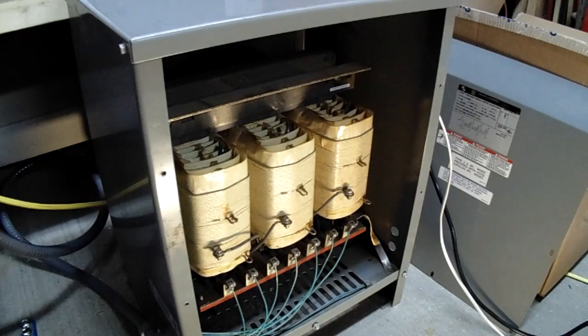And if you didn't know, that's actually completely legal to do in a professional installation by a contractor. And you do have to derate the transformer sometimes, and what I mean by that is this is 11 kVA, and if I wire it backwards I might only be able to use 9 kVA of that, and a kVA is a kilovolt amp, for those of you that don't know. So I want to use this as a step-up and step-down transformer, and primarily for a rotary phase converter that is only 240 volts right now, that I want to be able to convert up to 480 volts 3-phase.